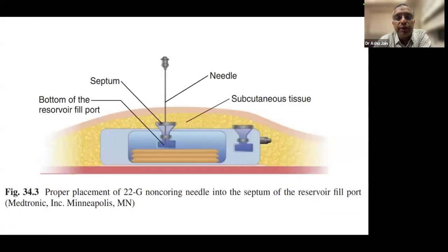This is how you have to do this. So this is how your needle goes. If you see, the central port is for the drug, and the one in front is for the CSF. So you should be very careful. It is slightly projecting so that you can feel that membrane under the skin. You can see this is projecting.